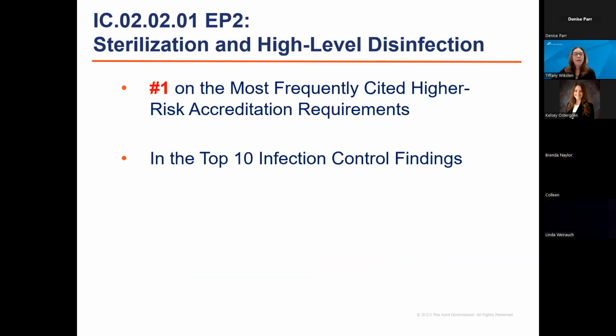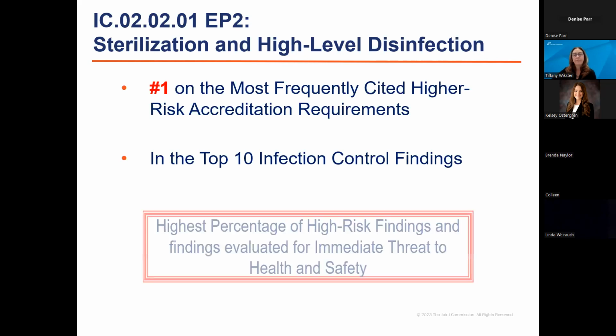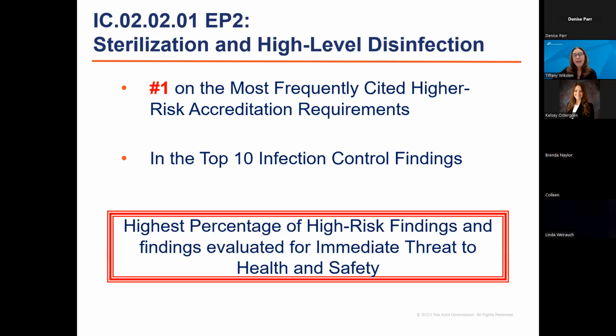We're going to talk a bit about IC 020201 EP2 sterilization and high-level disinfection because it is the #1 most frequently cited higher risk accreditation requirement for hospital program, the ambulatory program, and in the top 10 infection control findings for programs that have sterilization and high-level disinfection. It is also where the highest percentage of high risk findings and findings evaluated for immediate threat to health and safety live.